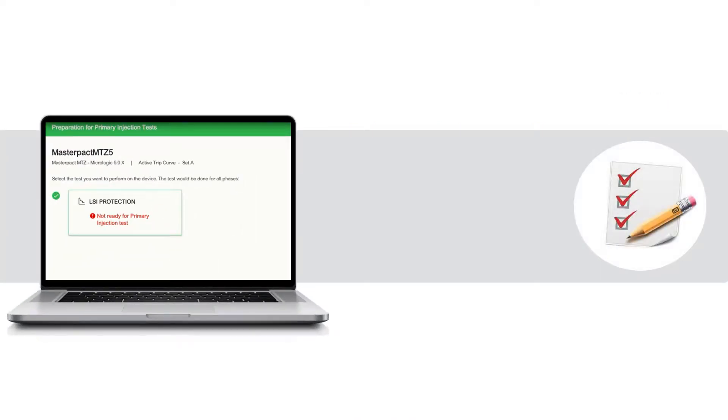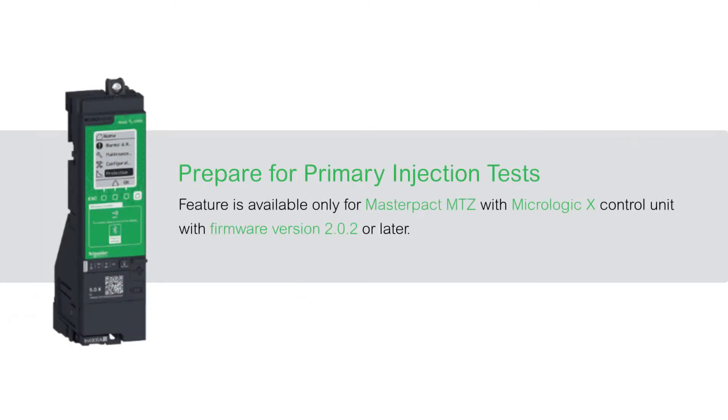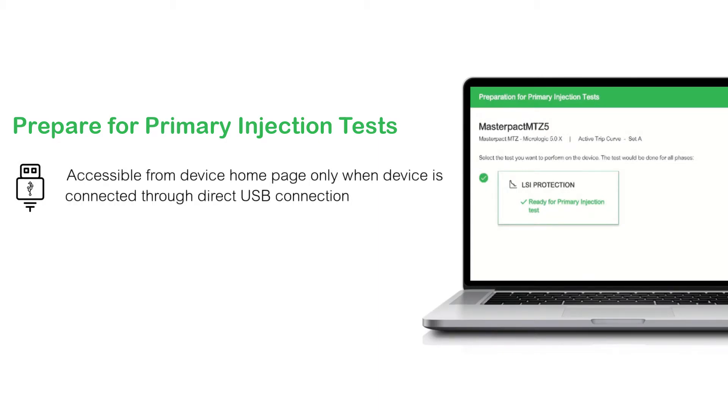EcoStruxure Power Commission software helps you to fulfill some preconditions before you perform the actual tests. Note that this feature is available only for Masterpact MTZ with MicroLogic X Control unit with firmware version 2.0.2 or later. The Prepare for Primary Injection Tests feature is accessible from the device homepage only when the device is connected through direct USB connection.